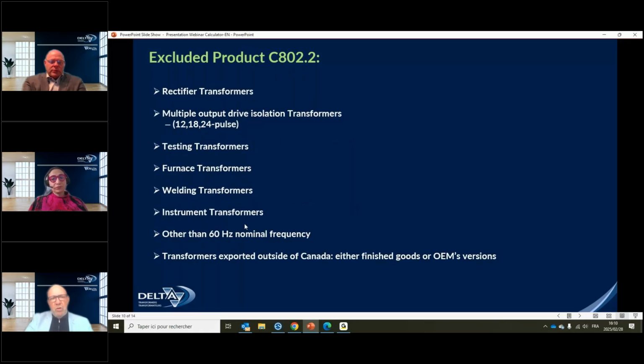All the specialty products, like rectifier duty transformers, multiples, drive isolation, testing transformers, welding, current transformers, and anything that doesn't have a 60 hertz nominal frequency, they're all excluded. So if you have to deal with those types of transformers and the efficiency and heat rejection are important, ensure that you compare apples to apples and ask your manufacturer for the right information.